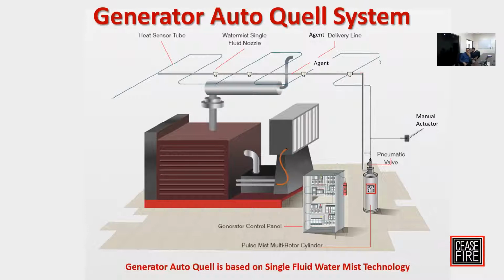This schematic shows you how the complete system works. I'll move my arrow here, and this is my agent container, which has a pulse mist multi-rotor cylinder inside, where at the bottom of the dip tube we have rotors. The rotors mix the water and the nitrogen, which is filled as a propellant, creating a bubble effect. And from here, you have a pneumatic valve, which is connected with the tube.